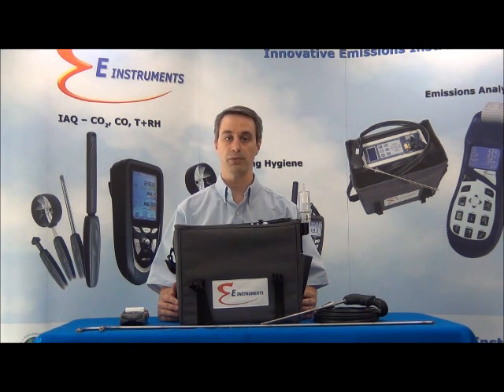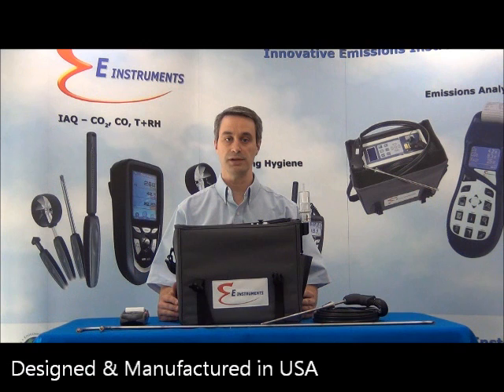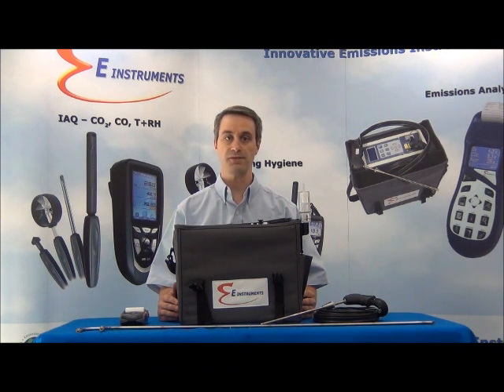The E5500 Portable Emissions Analyzer is completely designed and manufactured in the United States. The E5500 can be configured to measure up to 5 gases, including oxygen, CO, NO, NO2, and SO2 with electrochemical type gas sensors, along with a calculated CO2 value.